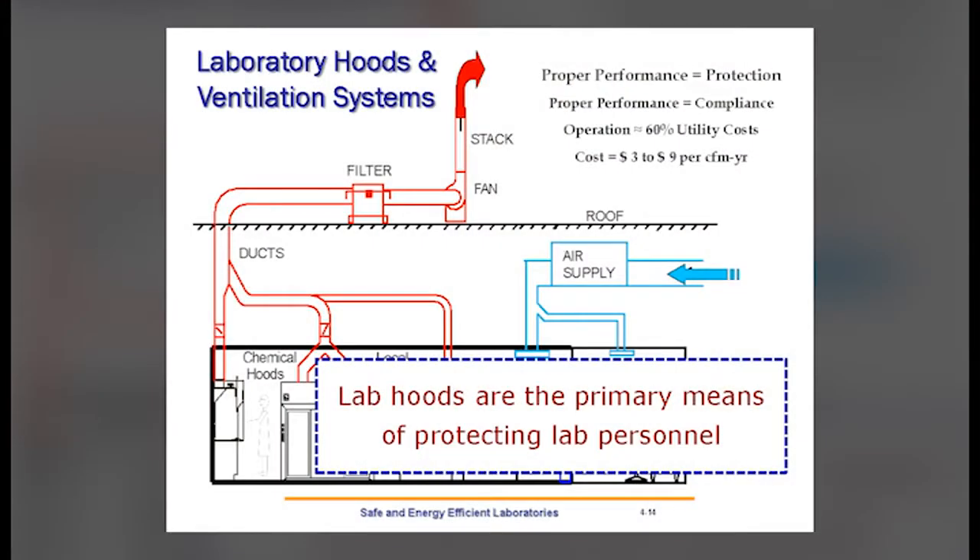When we look into laboratories, we see lots of different types of devices: fume hoods in lots of different shapes and sizes, biological safety cabinets, glove boxes, ventilated balance enclosures. In fact, there are about 700 different types of exposure control devices typically employed in laboratories. All of those have to be evaluated, assigned appropriate airflow specifications, and tested — not only on a commissioning basis but on a routine ongoing basis. The hood provides primary containment and the laboratory environment provides secondary containment. What escapes the hood stays within the laboratory; if there's a spill outside the hood, it stays within the lab and does not migrate to non-laboratory spaces.